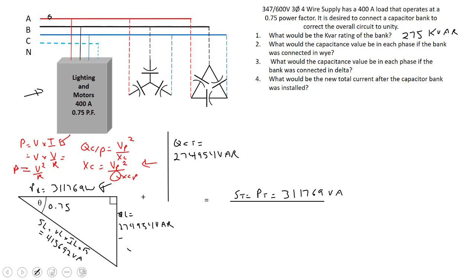First thing is take our QXC total and determine how many VARs per phase. QXC total is the same as saying QC of the phase times 3. Moving that around, QC per phase equals QXC total divided by 3. In our case, we're going to take our 274,954 VAR and divide by 3. That's going to come to about 91,651 VAR per phase.